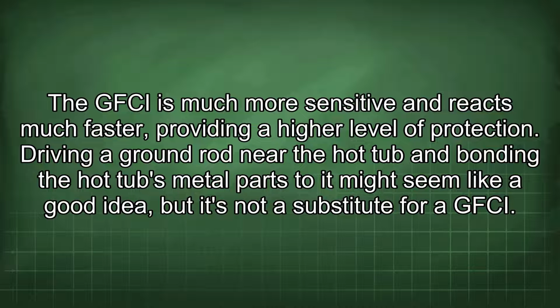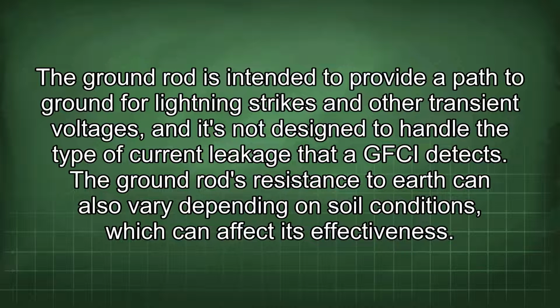Driving a ground rod near the hot tub and bonding the hot tub's metal parts to it might seem like a good idea, but it's not a substitute for a GFCI. The ground rod is intended to provide a path to ground for lightning strikes and other transient voltages, and it's not designed to handle the type of current leakage that a GFCI detects. The ground rod's resistance to earth can also vary depending on soil conditions, which can affect its effectiveness.